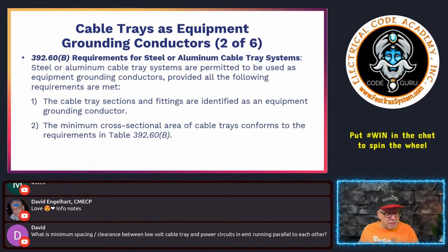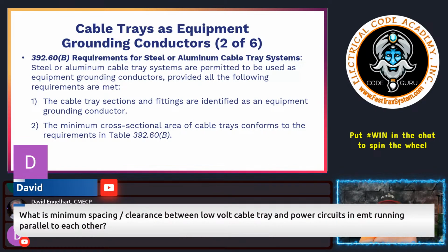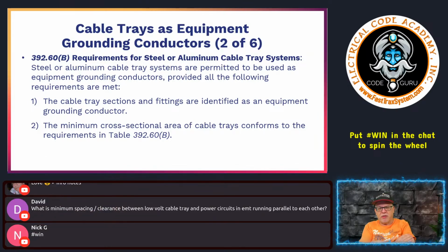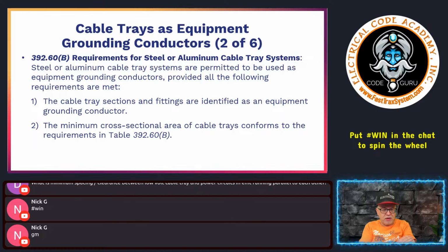David's asking about the minimum clearance. Typically, if you're going to have power in there and you have low voltage, then you're going to have a separator, something that separates between them. That's going to be a separator or divider because you'll be intermixing those types of things. If you have low voltage, the rating is probably less than 600 volts. So you're going to have some type of separator in that tray in order to create a separation. They do make separators that go in cable trays. Total pain in the butt, personally, to try to achieve that in there.